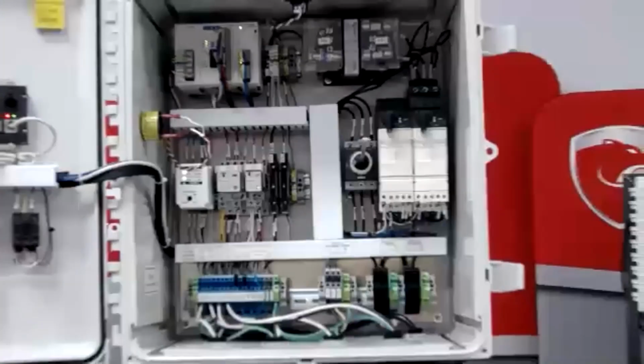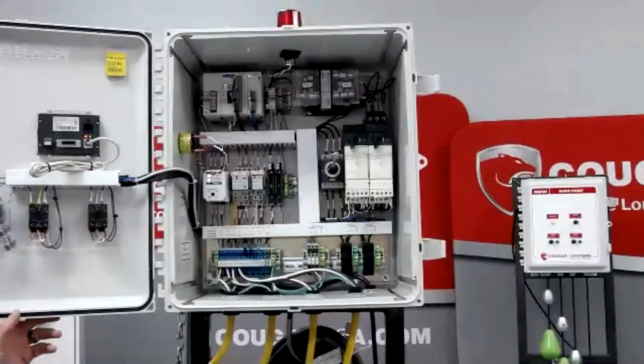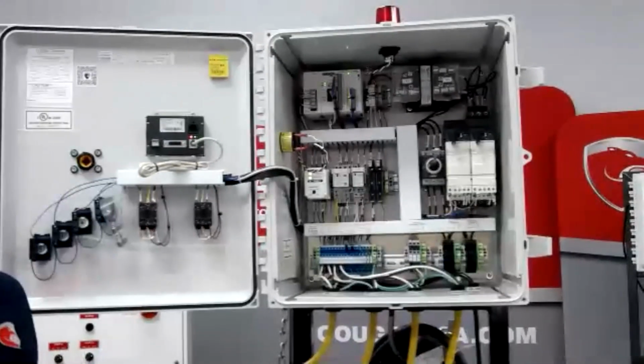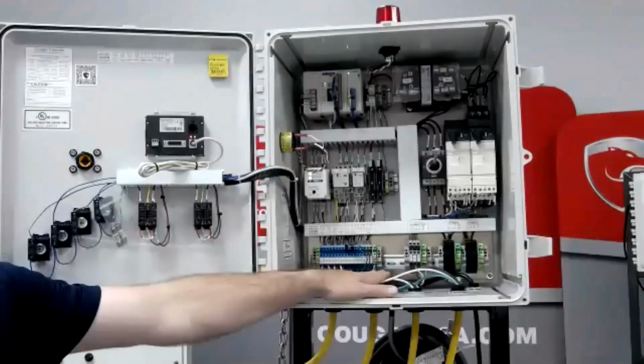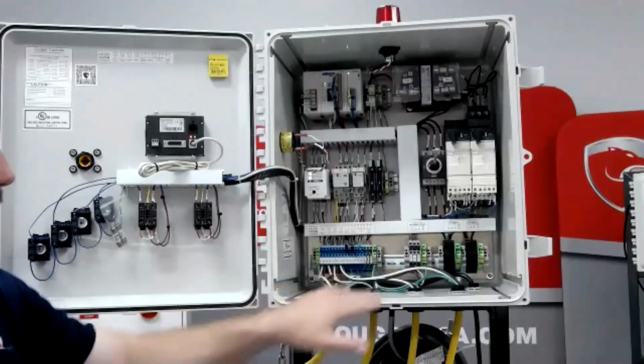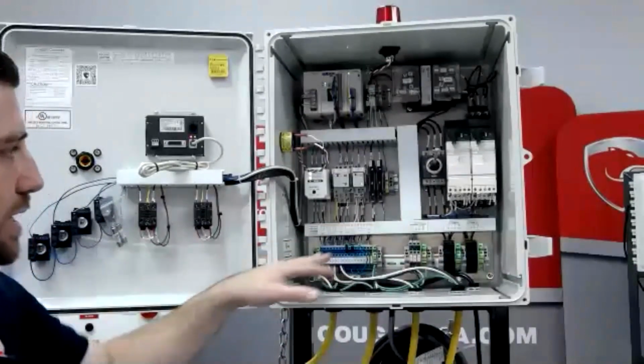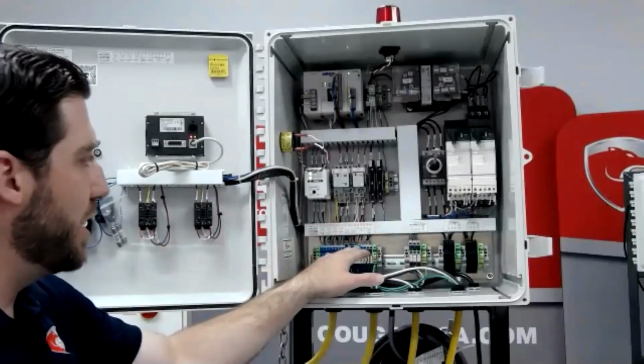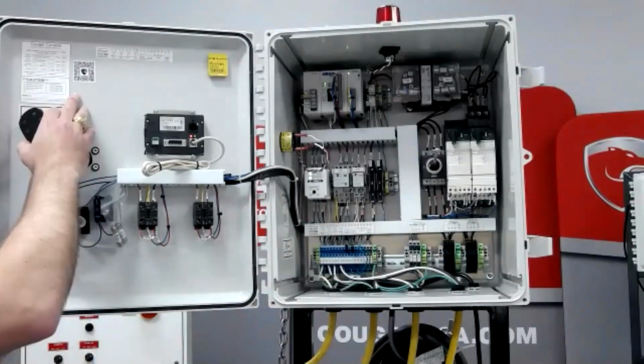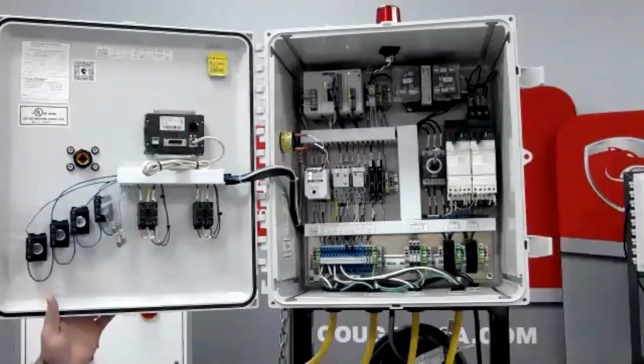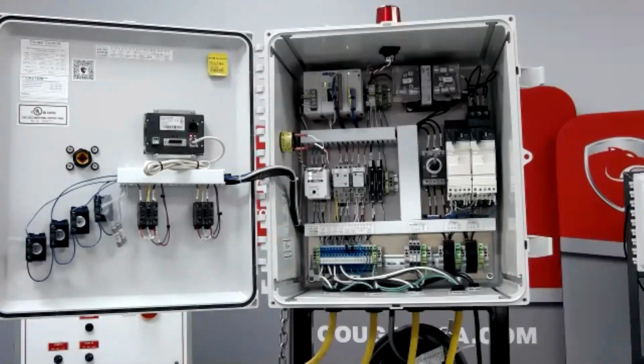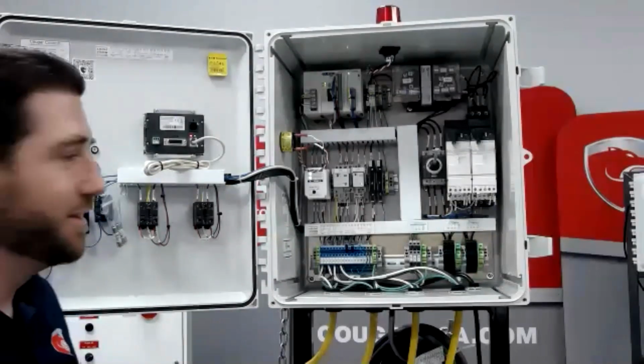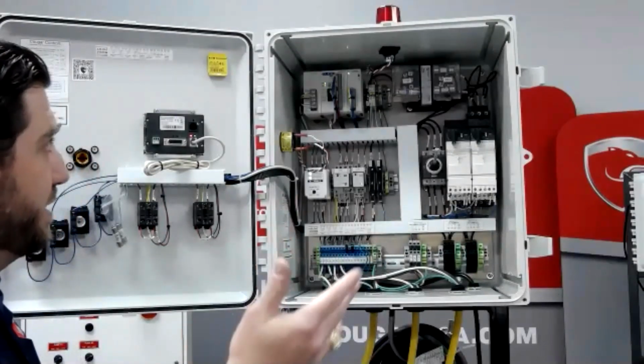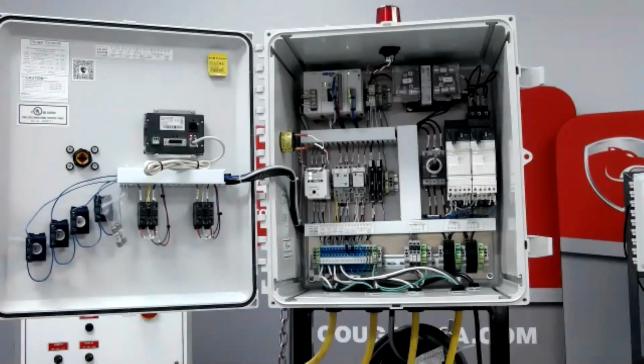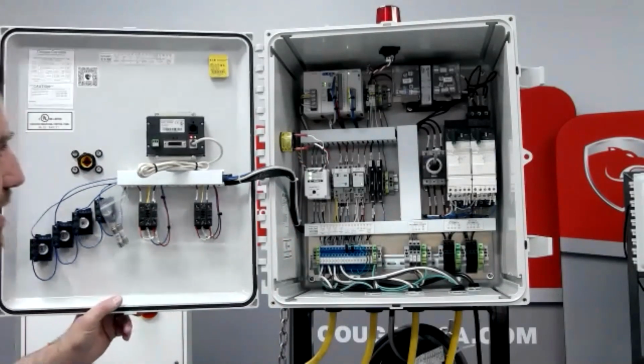Another thing, you can see there's a lot of little features in here that come from our experience in the field. Again, having these up on a 45-degree angle makes it easy to make the field connections. Everything is labeled, and all of these labels correspond back to the wiring diagram, as well as having QR codes to be able to scan and get to those drawings. We provide them as a folder in the panel, but a lot of times those can grow legs on the job site and walk away. So you can always scan to get those back, as well as having all of the relevant information there if the people on site ever need support.